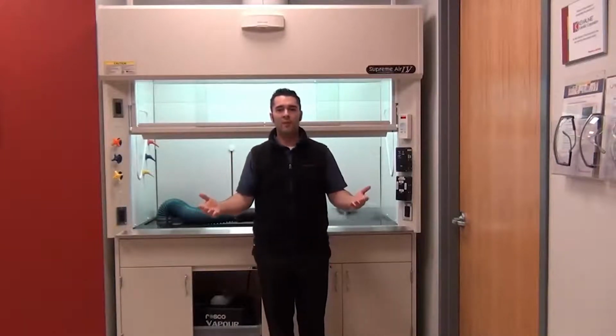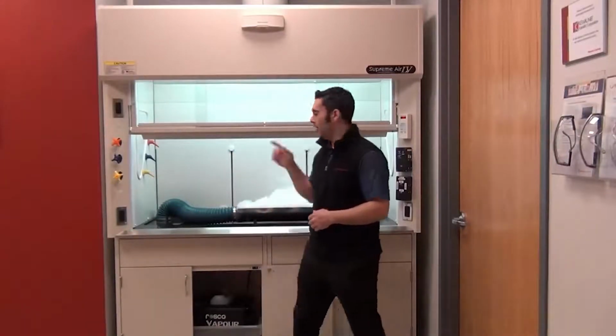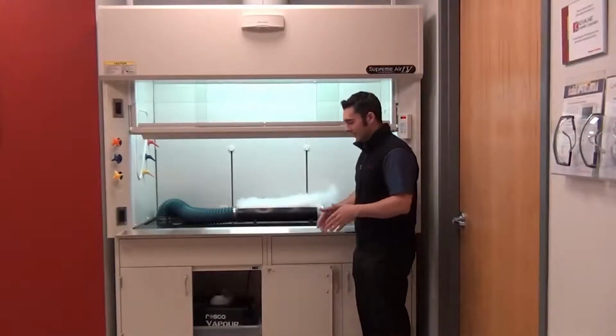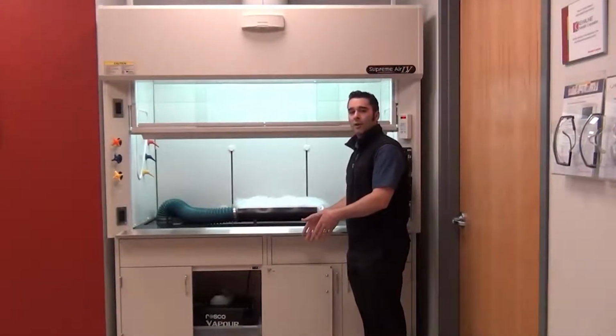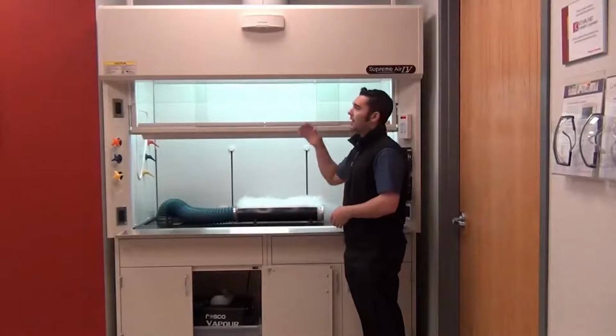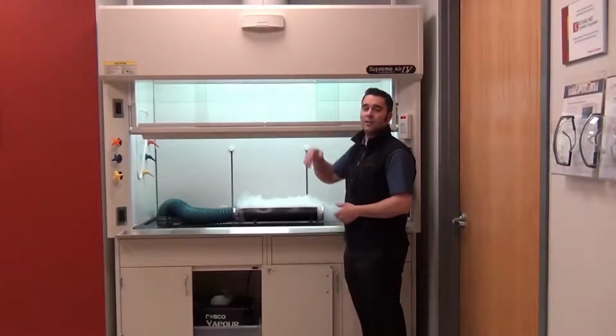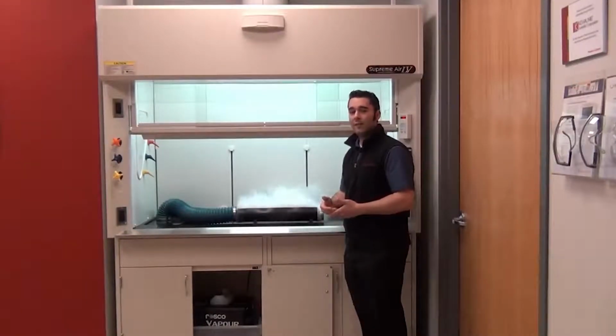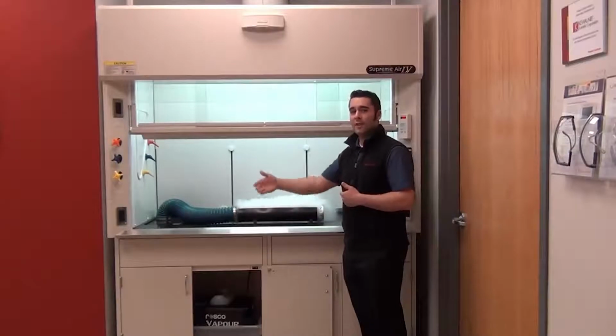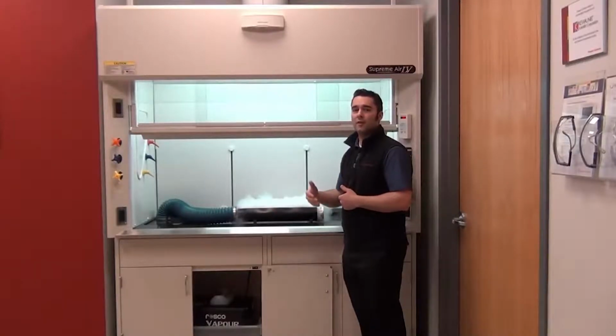So you won't be realizing the energy savings that you need. With the Phoenix Controls Zone Presence Sensor, I map out a very narrow window in front of the fume hood, and I can set the delay that this has. So I can set it as low as 5 seconds or as long as 5 minutes or 10 minutes if I wanted to trigger the setback.